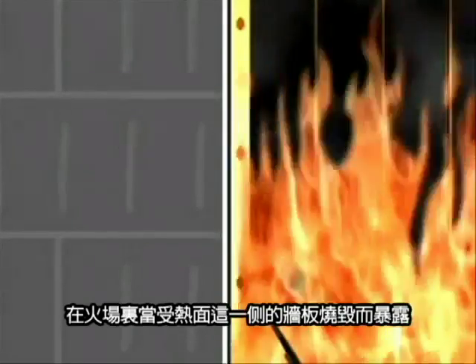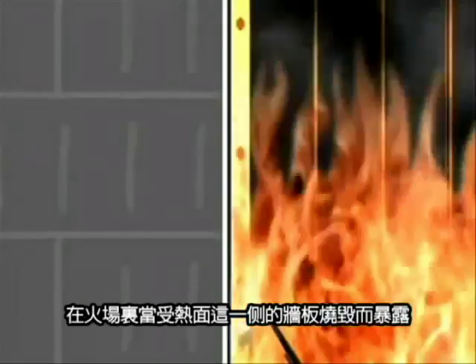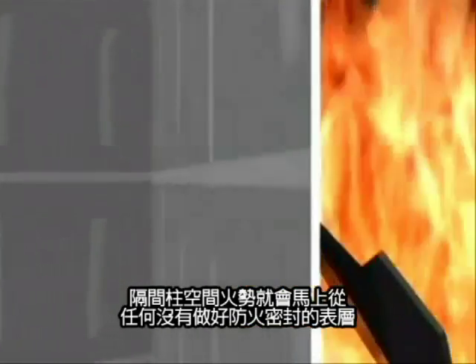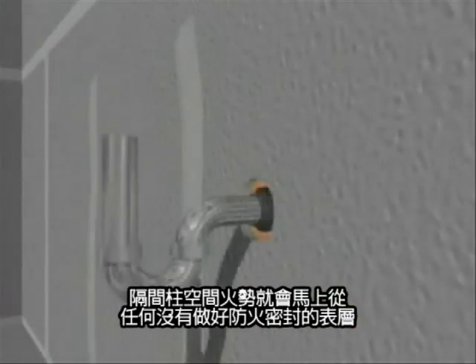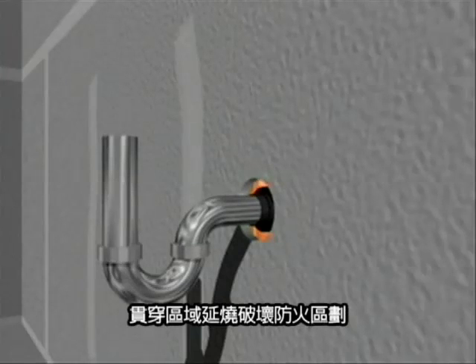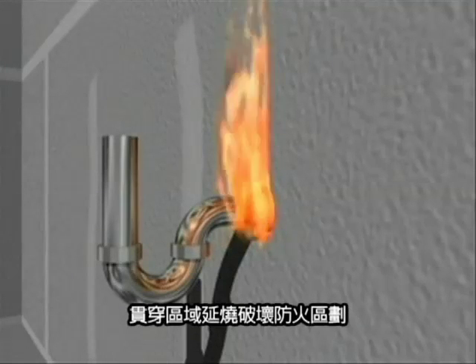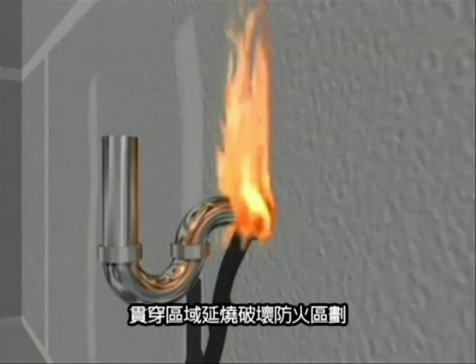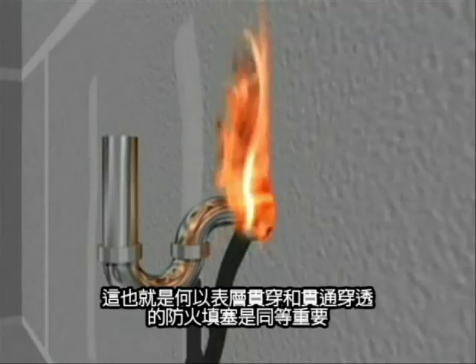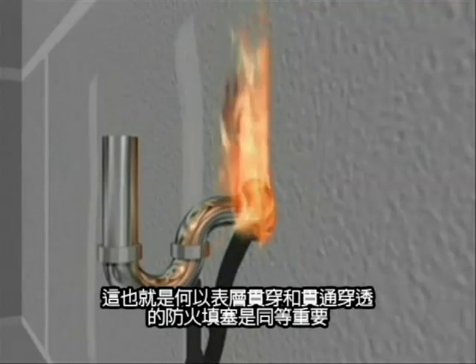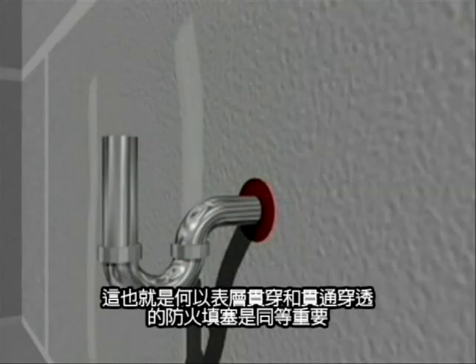In a fire, as the layer of wallboard on the hot side fails, exposing the stud cavity, any unsealed membrane penetrations on the cold side instantly permit the products of combustion to be forced through the opening, breaching compartmentation. This is why it is just as important for membrane penetrations to be fire stopped as it is for through penetrations.